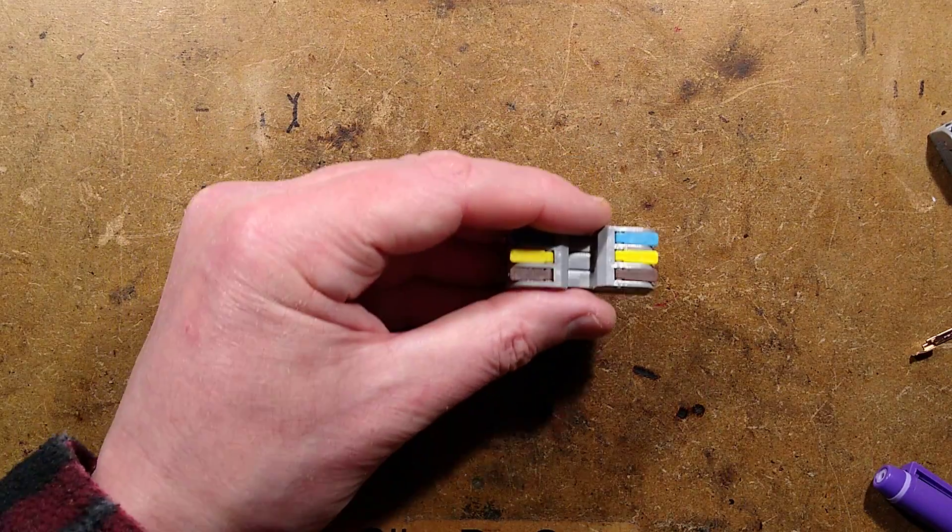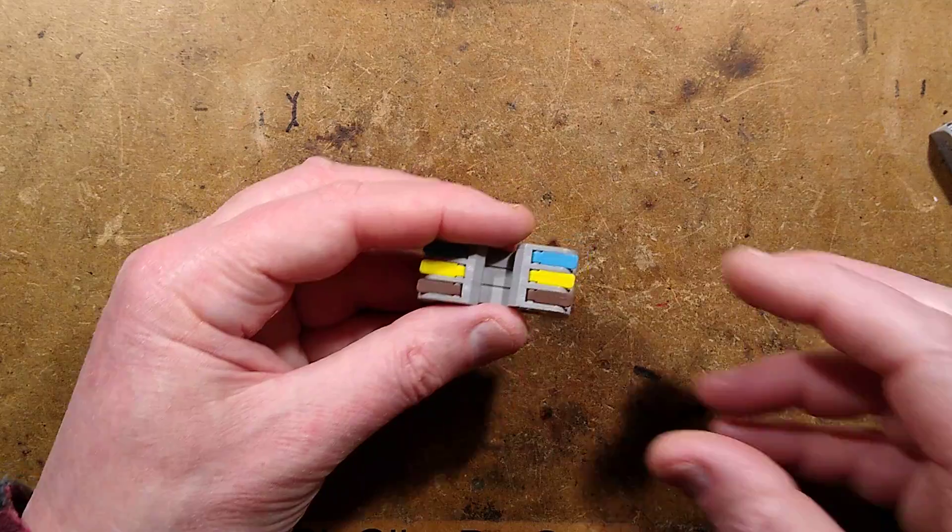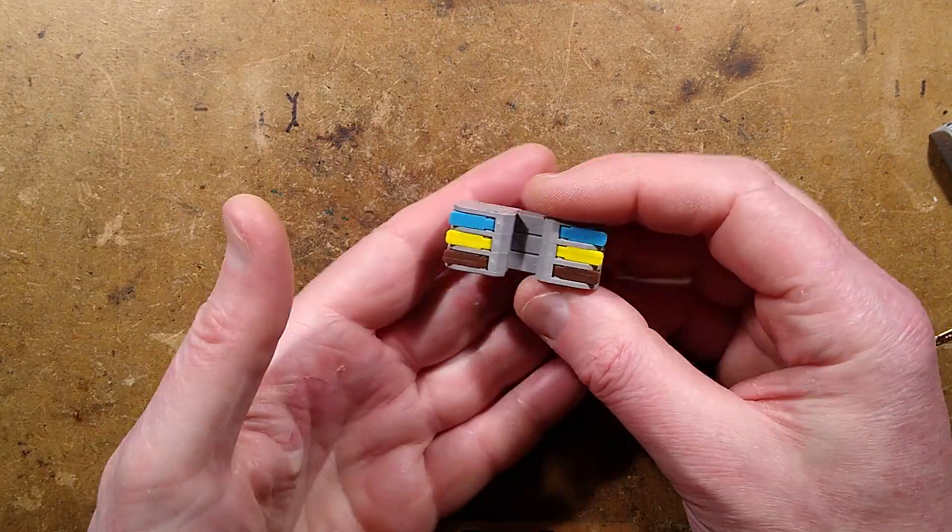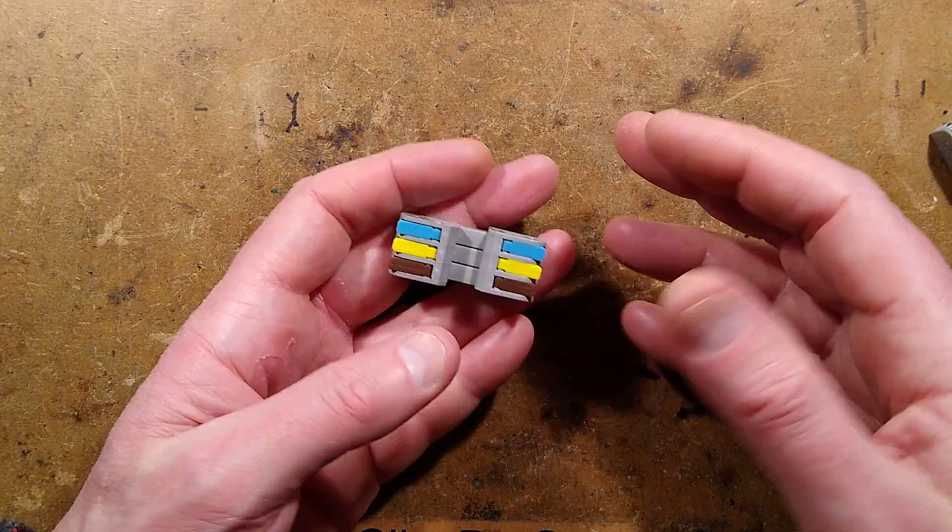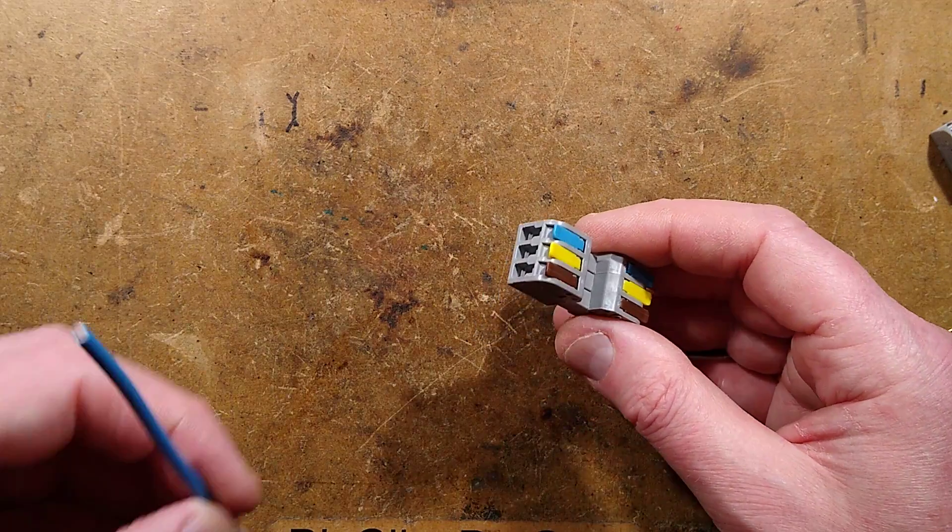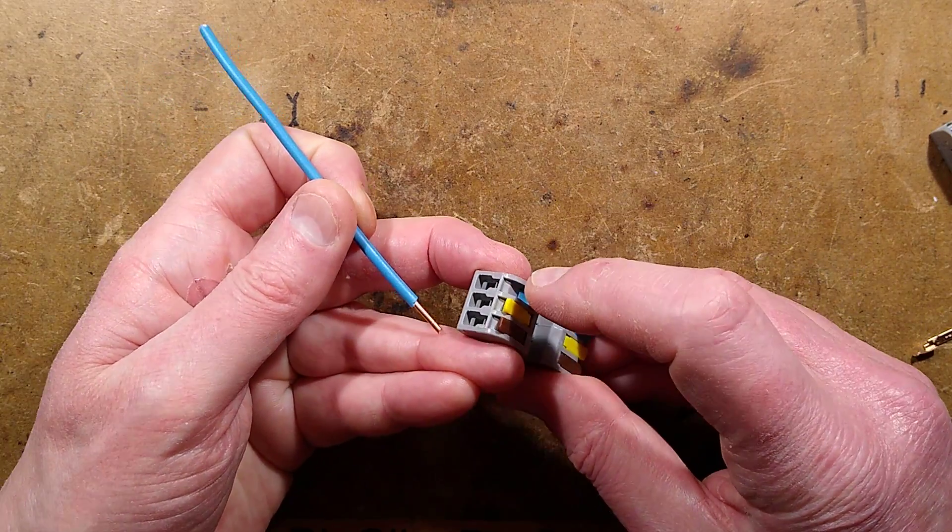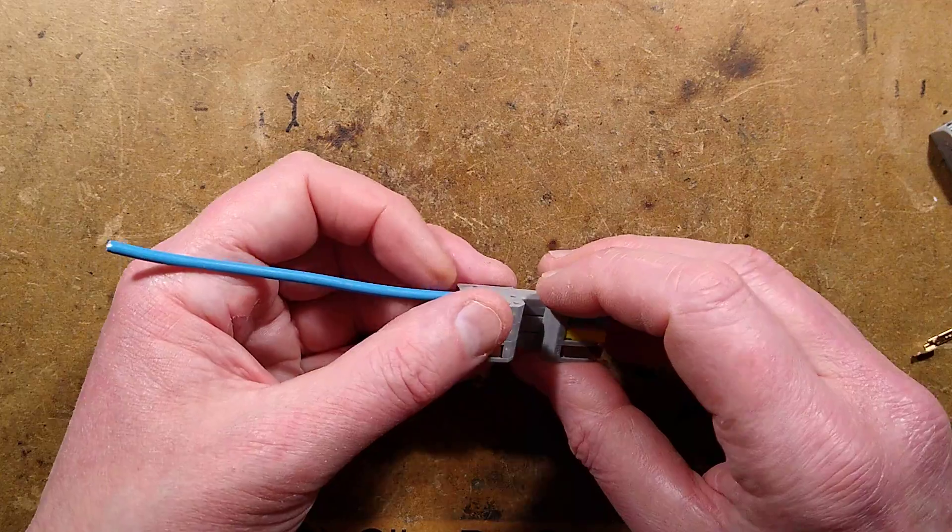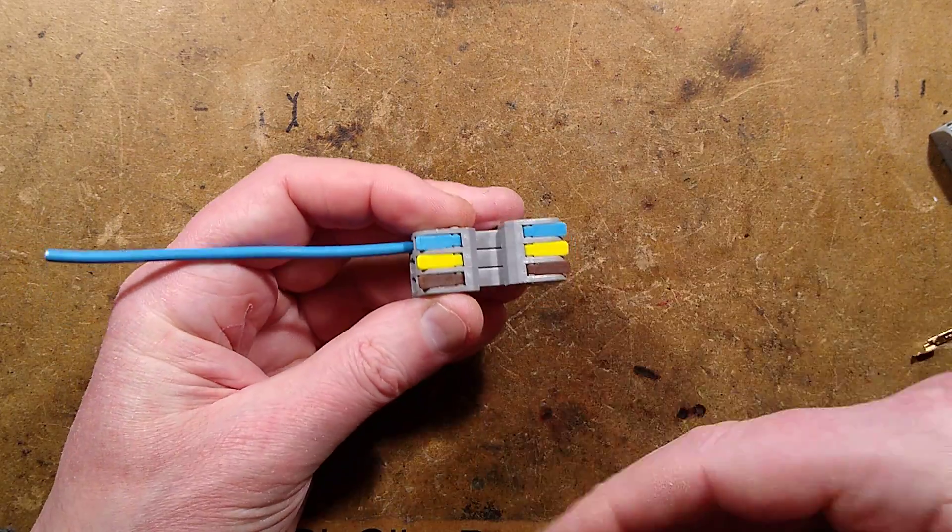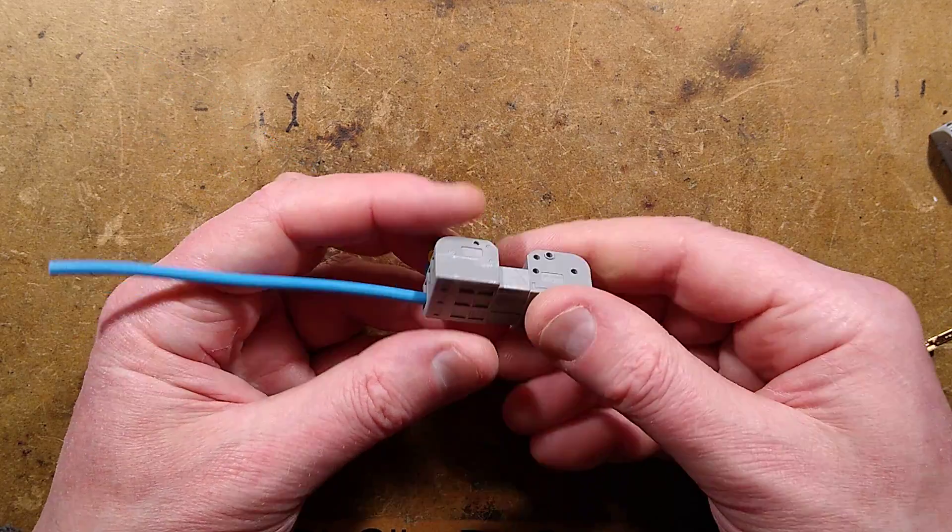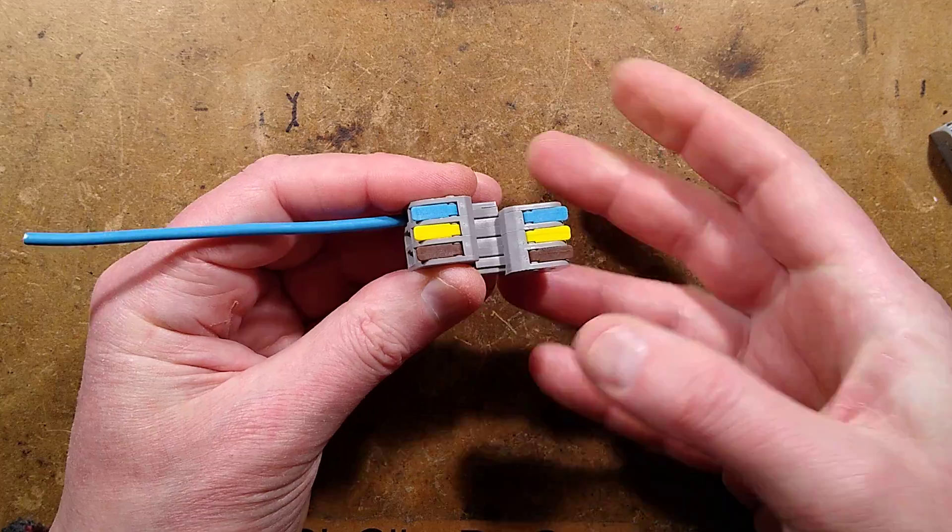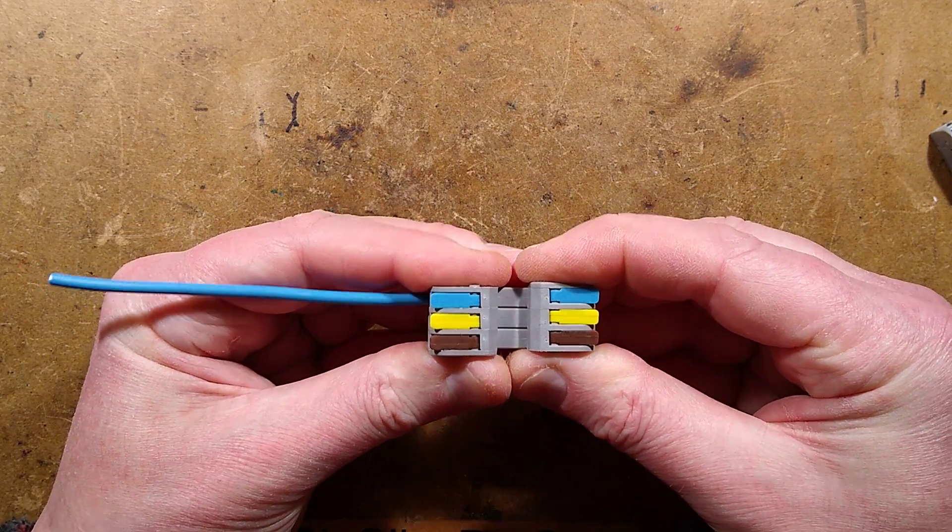So it is an interesting connector. I like the concept, I like the universal modular approach. I would say that these are not something I would ever use in a commercial job. I wouldn't install them in someone's installation, because there's always the risk that you're going to potentially have an incident with the connector and something's going to go on fire. And then, because these are unregistered, uncertified, that would be an issue. And also, if someone got electrocuted as a result of doing exactly what I said earlier, of actually misleading them, that could be something that could come back and haunt you, so to speak.